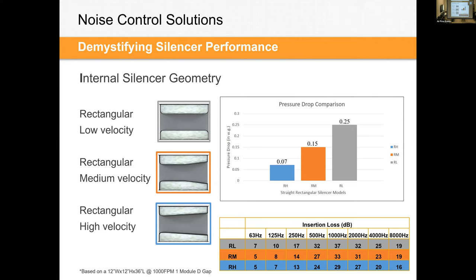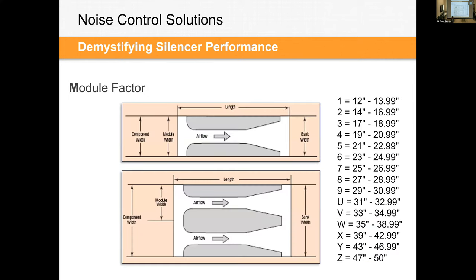And you can imagine continuously changing this from a parallel baffle and also the free area. You can really fine tune these silencers to give you a wide range of performance. If you use like the RH, you're going to have low pressure drop. If you use the A gap or that 57.5% free area, you're also going to have low pressure drop. So they pair together. The final factor is module factor. And this one's a little bit convoluted, so I'll try and make it explicitly clear. But basically, there's different module factors that can be applied to a silencer.